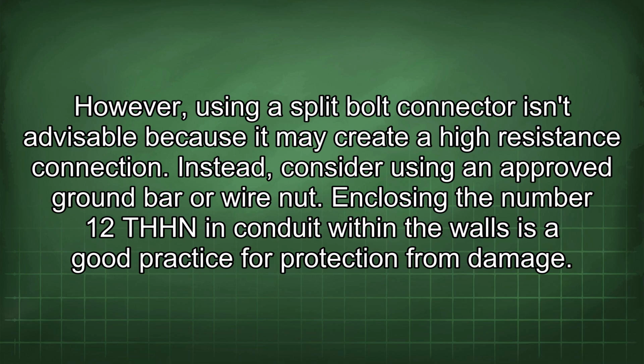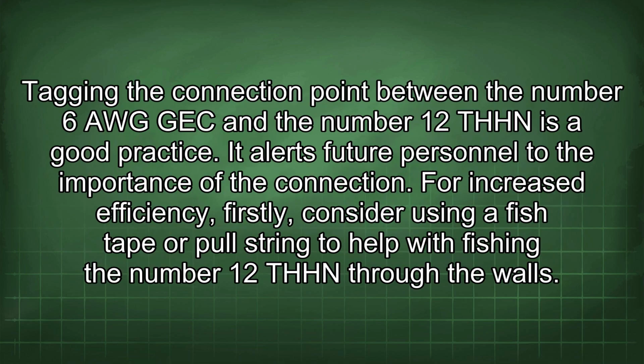However, using a split bolt connector isn't advisable because it may create a higher resistance connection. Instead, consider using an approved ground bar or wire nut. Enclosing the number 12 THHN in conduit within the walls is a good practice for protection from damage. Tagging the connection point between the number 6 AWG GEC and the number 12 THHN is a good practice. It alerts future personnel to the importance of the connection.